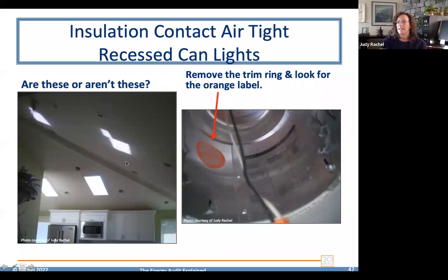The lighting in our houses, especially in our older homes: there's still a lot of lighting that cannot have insulation in contact. So IC, insulation contact, or airtight recessed light cans. Just looking at them, particularly from inside a home, we can't tell. We need to remove trim rings and look to see if there's the label, looking for the model, which will hopefully tell us whether it's IC. This orange label tells us it's ICAT, which is insulation contact airtight.